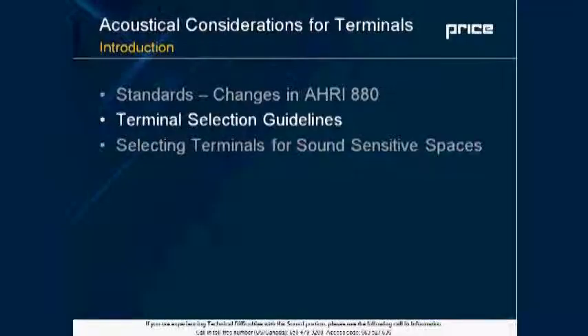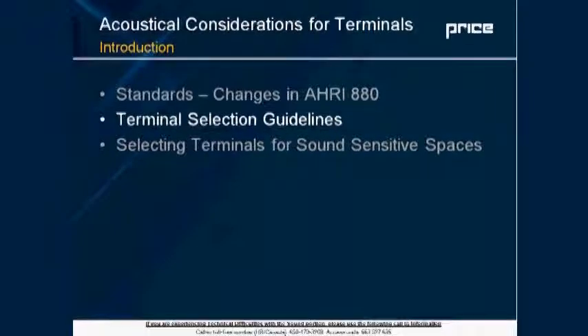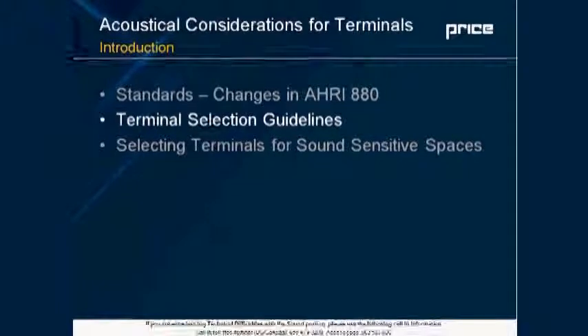Today I'll be talking about terminal selection guidelines, primarily focusing on the acoustical aspects. There are many factors to consider with terminal selection, but today we'll focus on acoustics. The terminal units we'll examine are single duct boxes and constant volume fan-powered terminal units. The factors we'll consider and their influence on acoustics are: flow rate, differential pressure, unit size, liner type, and sound attenuator silencers.